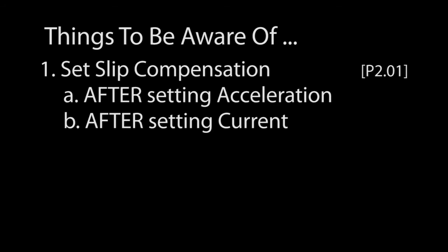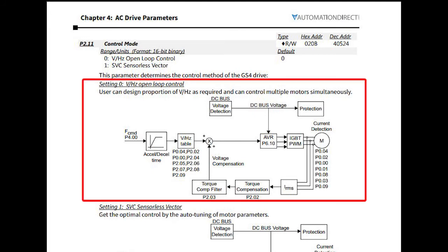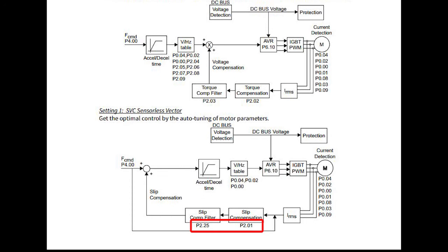We used parameter 211 to set the sensorless vector mode. If you look at the description of that parameter in the manual, you'll see block diagrams showing how the volts hertz and sensorless vector modes operate. What I really like about these diagrams is they also show you all the pertinent parameters you will want to use for each function — the volts hertz setup, the motor parameters you need to set, the slip compensation, the automatic voltage regulation, etc. I love that handy reference.